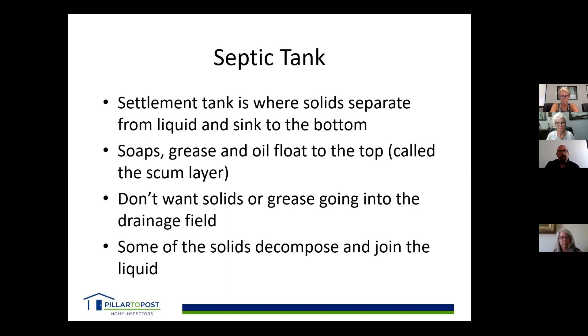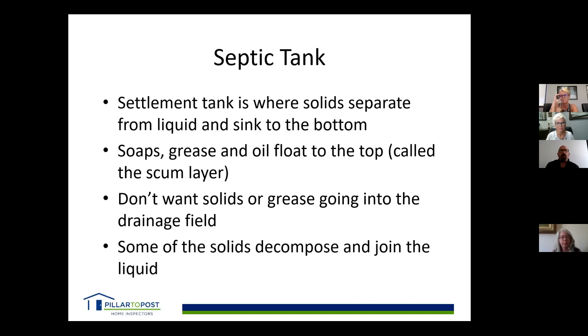The septic tank is your settlement tank — that's where all the solids go and separate from liquids. Greases and oils float to the top, which we call the scum layer. We don't want solids or grease and oils going into the drainage field, because that's where problems start. If solids and grease reach the drainage field, it will start plugging the system. Some solids in the tank will decompose.